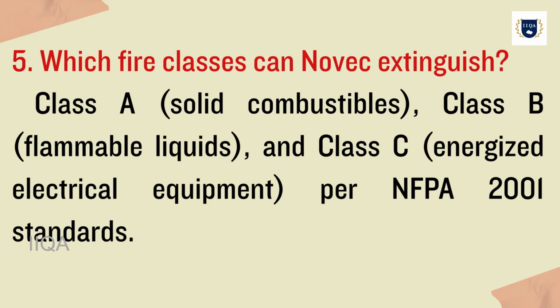5. Which fire classes can Novec extinguish? Class A, solid combustibles; Class B, flammable liquids; and Class C, energized electrical equipment, per NFPA 2001 standards.